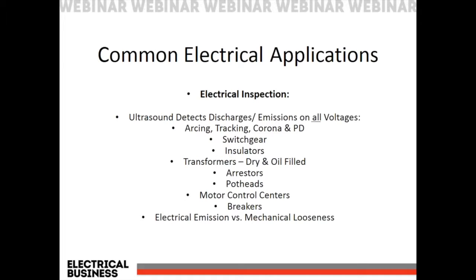Okay, so our common electrical applications. It's very simply put, we've got the standard stuff. Ultrasound detects discharges and emissions on all voltages, as I mentioned before. We can detect arcing and diagnose that it's arcing. We can detect tracking and diagnose that it's tracking, or corona or PD as well. We can do this in switchgear, insulators, transformers, dry and oil-filled arresters, potheads, MCCs, breakers, and again, as I mentioned before, we can determine whether this is an electrical emission versus a mechanical vibration or looseness happening in an asset.